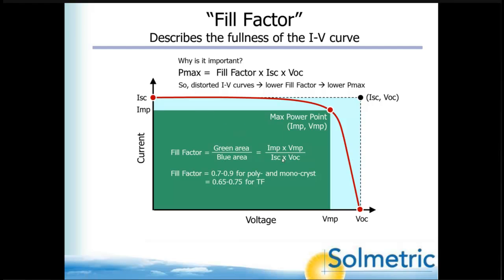And we're then taking ISC and VOC, multiplying both sides by that. So up at the top we get fill factor times ISC times VOC. So for a given ISC and VOC, the fill factor determines how much maximum power you can get. And that's really beautiful because anything that distorts the IV curve, like a change in slope anywhere or some notches caused by shading or soiling or shorted bypass diodes or something like that, or partly conducting, will show up as a distorted curve, leading to a lower fill factor, leading to lower maximum power.